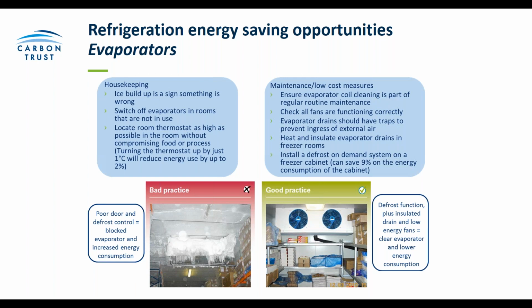And in terms of maintenance, again, making sure that the evaporator is cleaned when it's dirty. So the more dirty it is, the worse the performance of the system. So making sure that your technician is regularly cleaning and checking that the system is working. Again, checking fans are working and checking that drains are fitted with traps to prevent air being drawn in from outside. Again, insulation is also really important and useful in an evaporator.